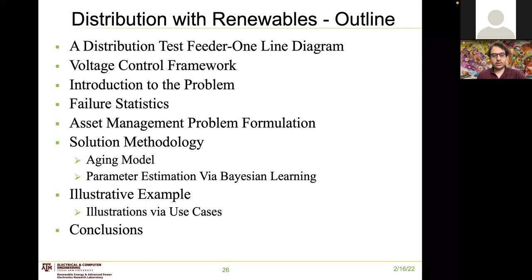Howdy all. I am Akib Rizada, and I'll walk you through a slightly different version of the asset management problem, one concerned with the lifetimes of switched mechanical devices such as voltage regulators and capacitor banks. We have those devices on our distribution feeders to provide voltage control and also do reactive power compensation.